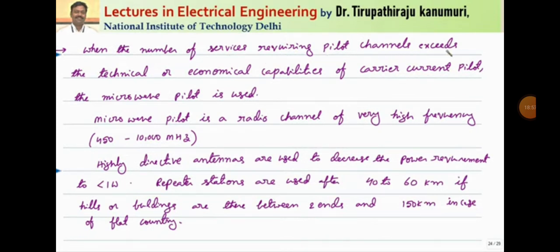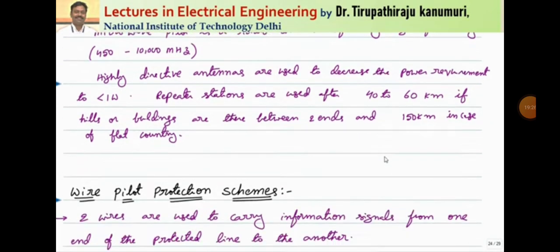When the number of services requiring the pilot channel exceeds the technical or economical capabilities of the carrier current pilot scheme — when more channels are required or more information should be transmitted — we go for microwave pilot protection. This microwave pilot protection is a radio channel of very high frequency in the order of 450 to 10,000 MHz. High directive antennas are used to decrease the power requirement, generally less than 1 watt. Where no barriers exist, we can transmit signals up to 150 kilometers without any problem. But if hills or buildings are present, microwaves get distorted, and repeater stations must be installed after every 40 to 60 kilometers depending on the attenuation.